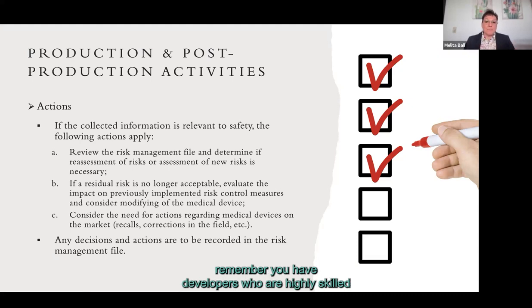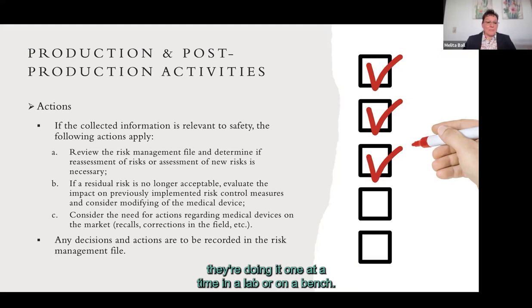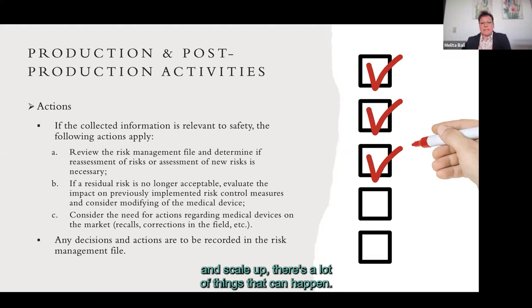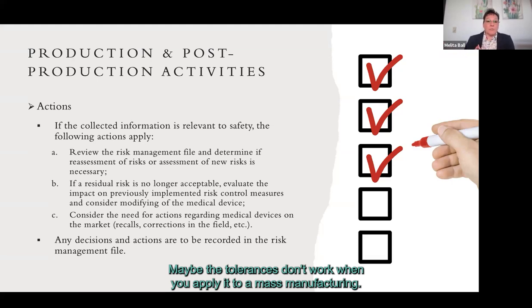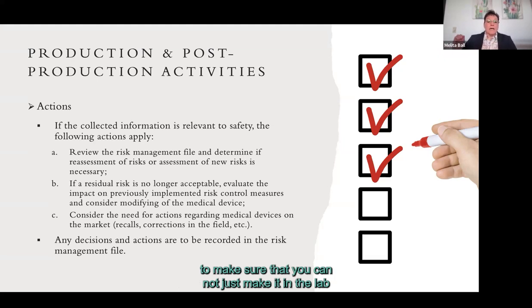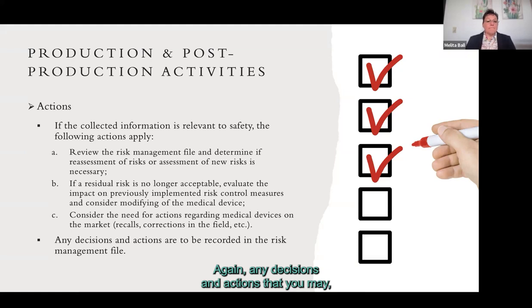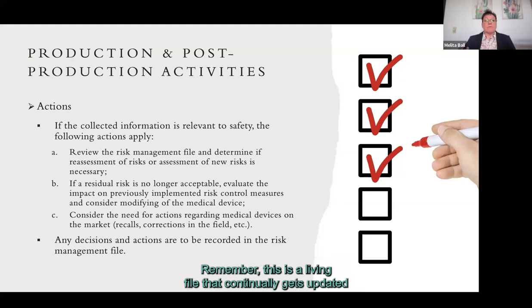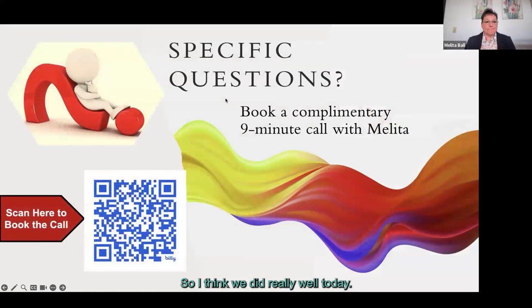A common issue when scaling from development to production is that developers make devices carefully one at a time on a bench; once you move to a full production environment, tolerances may not hold and adjustments are needed. Any decisions or actions coming out of post-production activity that feed back into risk management must be recorded in the risk management file. This is a living file that continually gets updated as you learn more about your medical device.